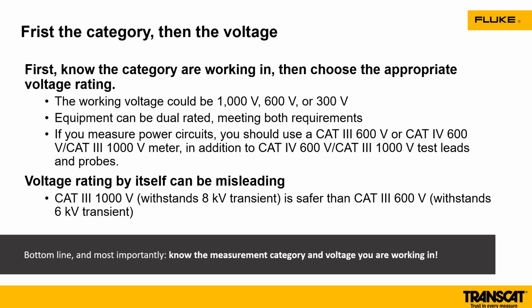So typically, you'll see on a meter a category 3 1000 volt, but it's category 4 600 volt. Or I've seen in some meters a category 3 600, which puts that category 4 at 300. That category 3 1000 volt can withstand that 8000 volt transient that we were talking about earlier, whereas a category 3 600 volt can only withstand a 6000.